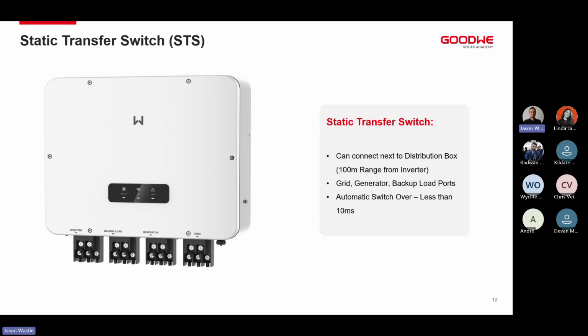So if we look at our backup port, it can change over and we can get power from the inverter, obviously the DC power that we're getting from the inverter, the PV and the batteries. Secondly, we can get power from the generator port. Thirdly, we can get power from the grid port, and all of that can run now into the backup port itself. So this is the switchover or transfer switch that we have with regards to the ET50.